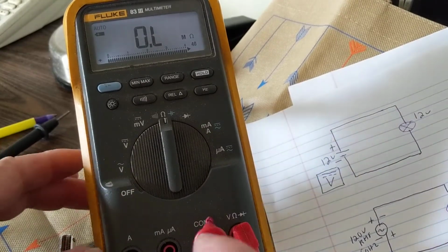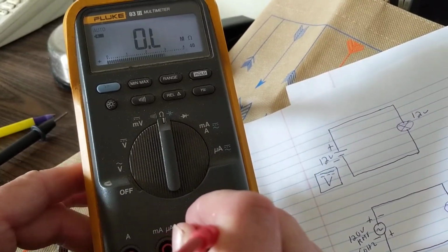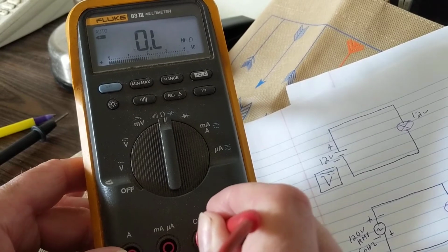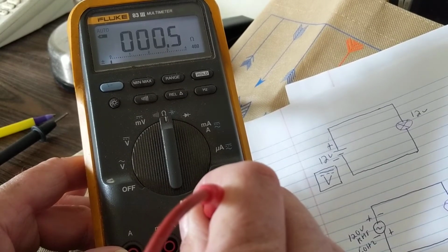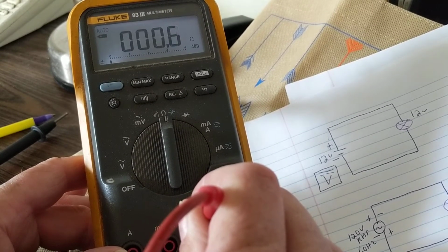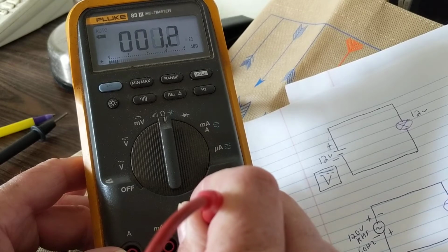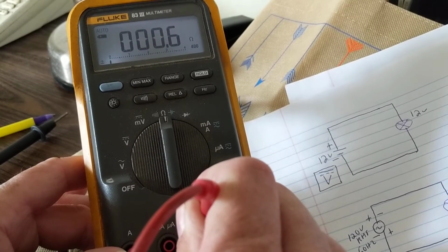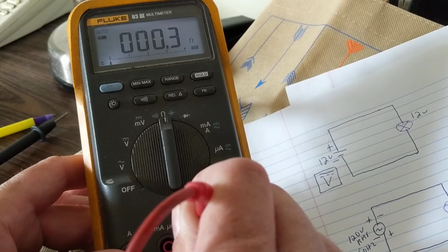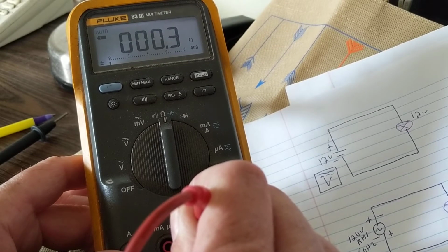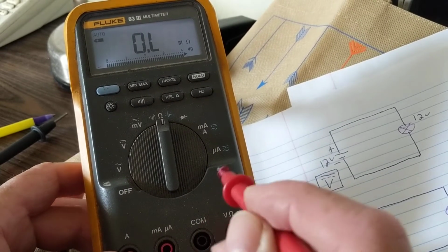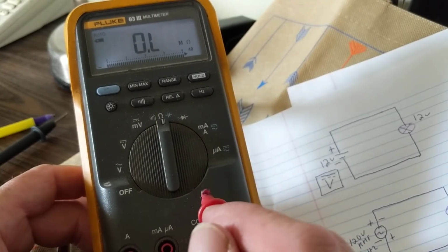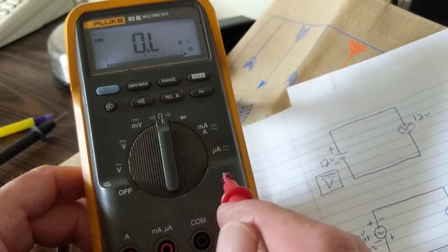How do I prove it? Put this in here and try to make contact. You see how you're making contact? That means this probe is good. You're measuring 0.3 ohms, which means I'm going from here to here. This probe is good, so the problem must be the other probe.